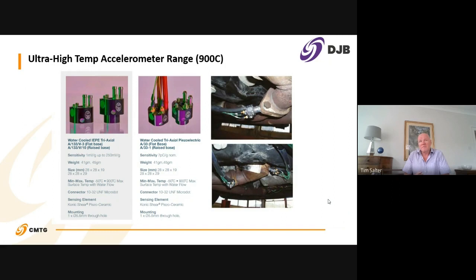For some applications, though, mainly automotive and some gas turbine test applications where you're on the very hot part, we produce a water-cooled version of an accelerometer which can measure up to 900 degrees, which is about 250 degrees higher than virtually anything else on the market. And the classic application, automotive, as I mentioned, is exhaust manifold and turbocharger type testing. Here you can see one mounted on an exhaust manifold. It's water cooled, so you need to supply it with a small water pump, something like a windscreen washer pump, and maintain the flow whilst the sensor is on the hot surface.